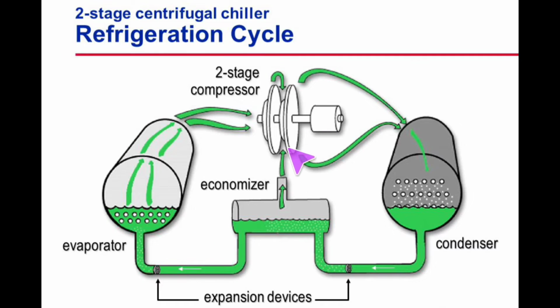One of the things that I did not mention here that I will just throw in very quickly is there is a second stage guide vane, but it's a very different design than the first stage, and it sits in between the two impellers, and it also looks very different. The armature that controls it is a very different design, so just be aware of that. There are two different sets of guide vanes on these machines. The CVHE series that has 3 stages also has just 2 guide vanes. There's not a third set of guide vanes in those, but the location stays the same in that the first stage and the final stage impellers are the ones that get those guide vanes.